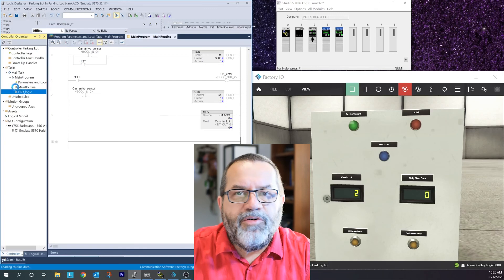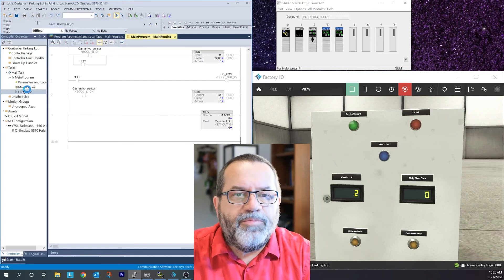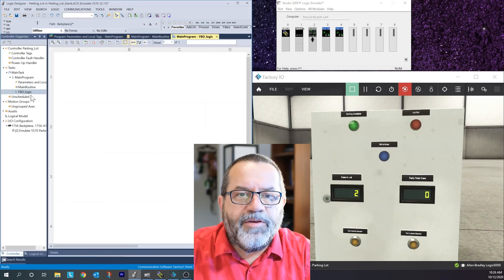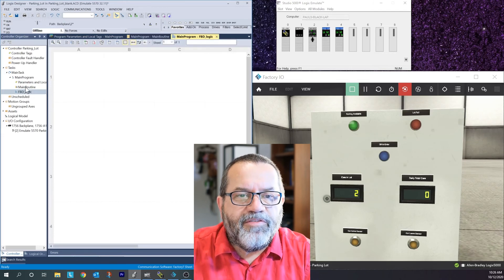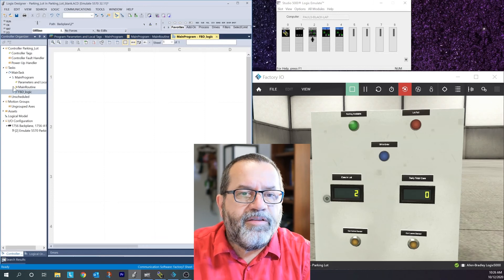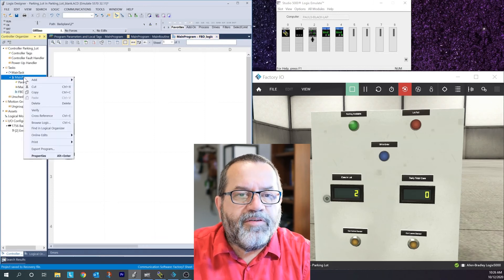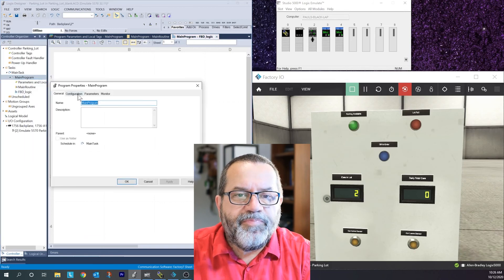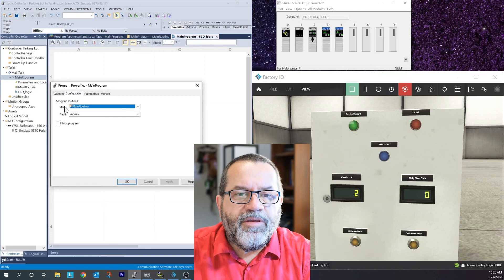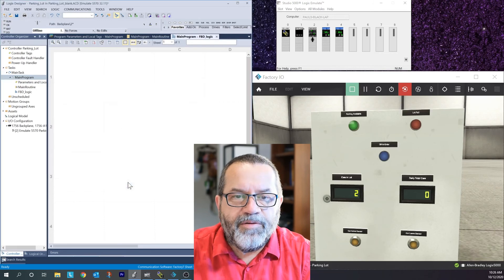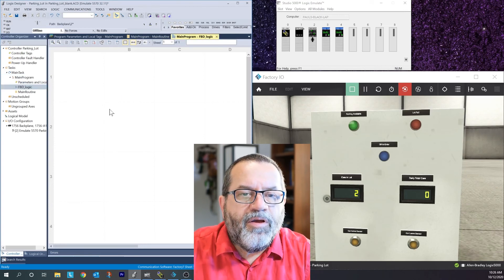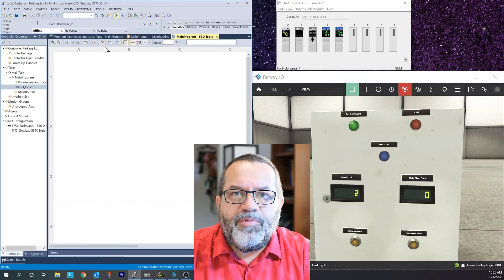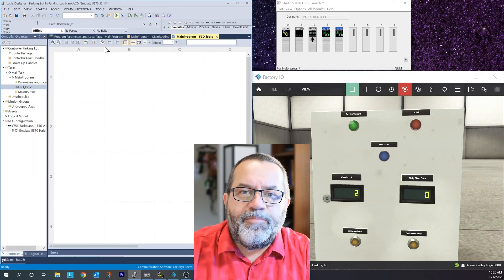Now I have two routines - the main routine that's automatically created when you open a project, and the new one called FBD Logic. This second routine is never going to run because my main routine doesn't have a jump to subroutine for it. So I'll go to properties on the main program and under configuration, assign routines - I'll change the main one to the new function block routine. Now when I run my logic it's only going to run this function block routine. I need some inputs, some outputs, and some logic.